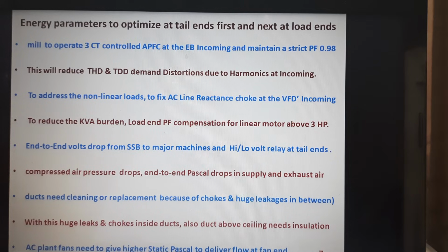At the tail end of the mill, let us try to maintain it at around 0.5 kg only. In the textile mill, because a lot of fluff is there apart from the yarn, the ducts get totally choked intermittently. This needs routine cleaning, and if the ducts have gone bad, especially the humidification ducts, because of water ingress in the air, they need to be replaced. The material of construction matters here, and the orientation of the duct also matters here.